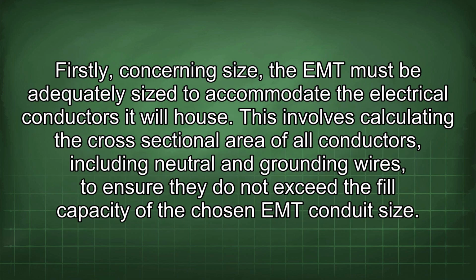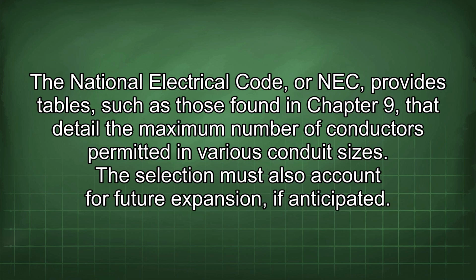Firstly, concerning size, the EMT must be adequately sized to accommodate the electrical conductors it will house. This involves calculating the cross-sectional area of all conductors, including neutral and grounding wires, to ensure they do not exceed the fill capacity of the chosen EMT conduit size. The National Electrical Code, or NEC, provides tables, such as those found in Chapter 9, that detail the maximum number of conductors permitted in various conduit sizes. The selection must also account for future expansion, if anticipated.